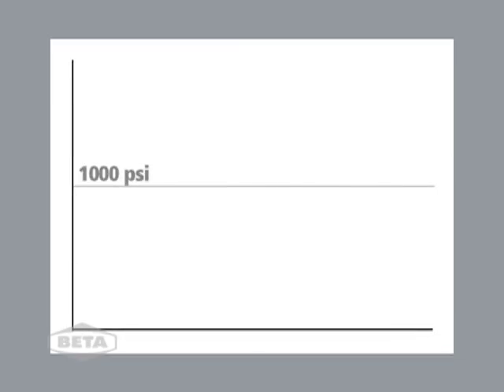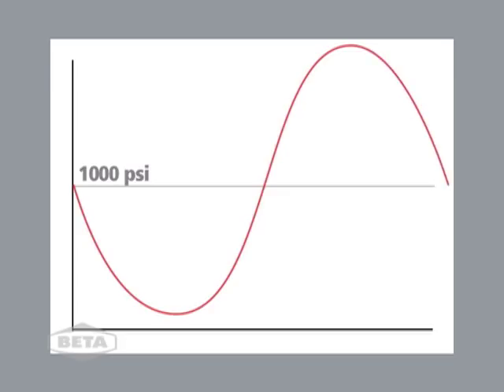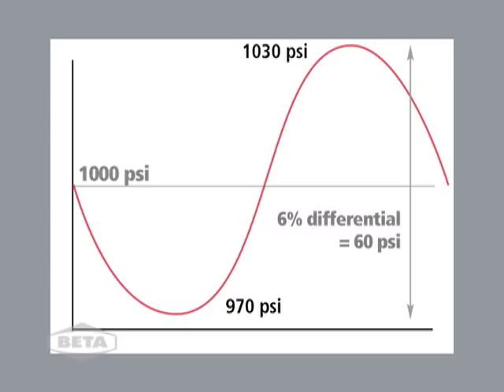The amplitude of these pressure pulsations can vary widely. Let's assume no pulsation control exists, and the pulsation levels can reach a relatively low amplitude of 6% peak to peak. The maximum is 1030 psi, and the minimum is 970. The differential pressure equals 60 psi between maximum and minimum amplitudes.